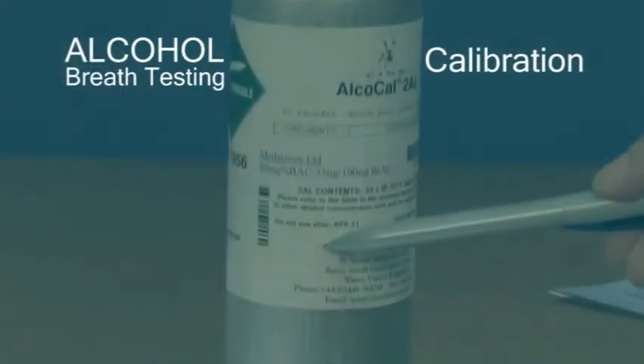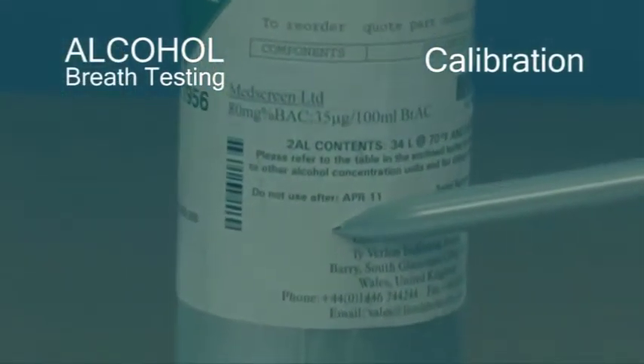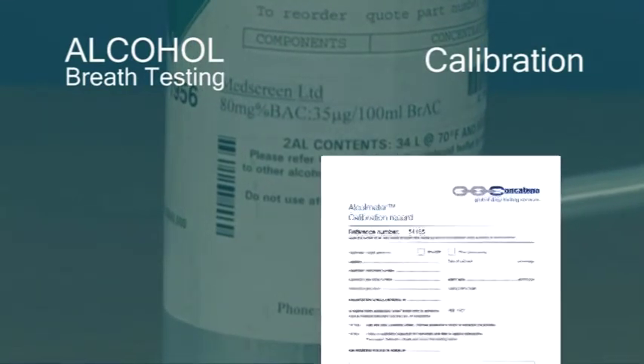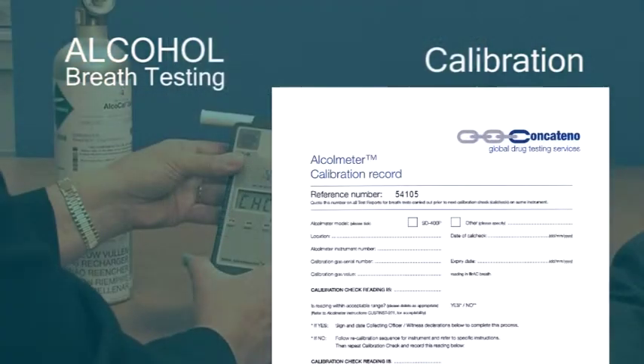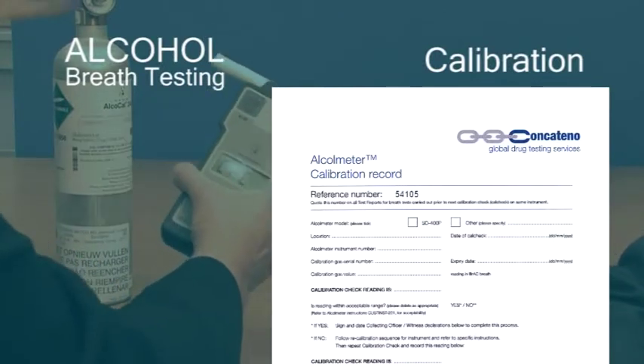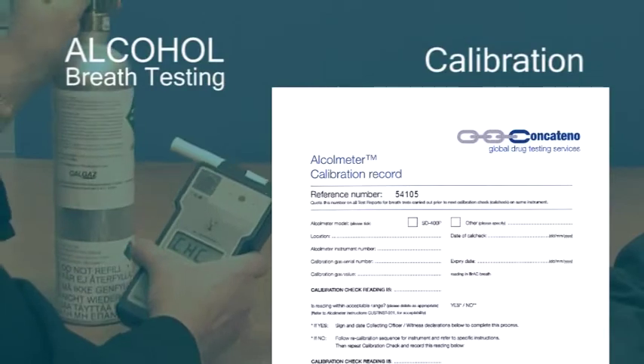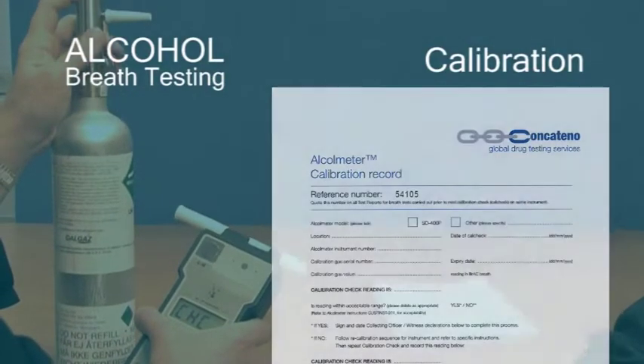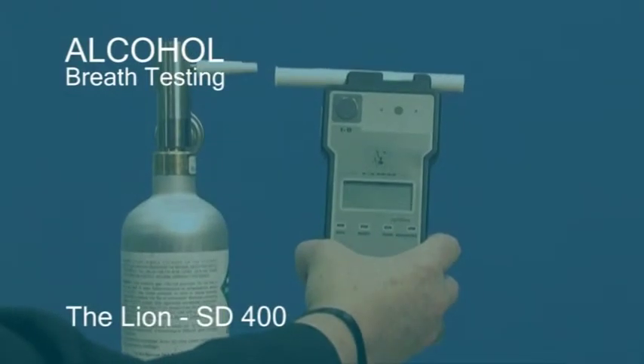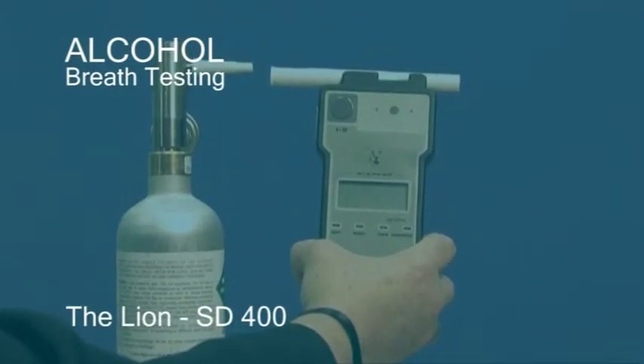You must make sure that your calibration gas is within its expiry date and record all the data required each time you check it or recalibrate it, even if you are doing this at home for your own training purposes. This provides a record of the machine's reliability. We will use the Lion SD400 as an example for the calibration check and recalibration.